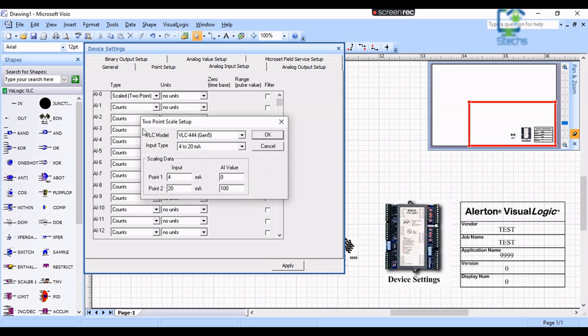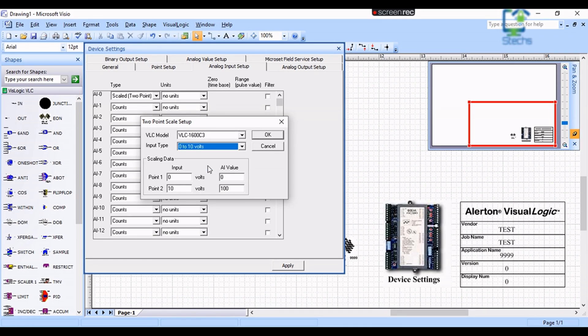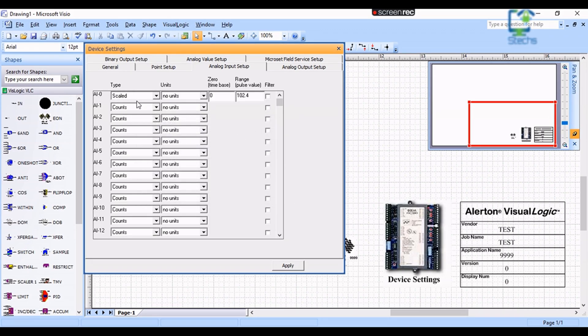When you choose Scaled Two Points, another window opens where we can enter the details of the controller we are using and the input signal type. We can provide the scaling data as shown in the video. Here I am entering the 0 to 100 range for a 0 to 10 volt DC signal, then click OK. Now you can see the values have been calculated and entered in the range columns automatically.